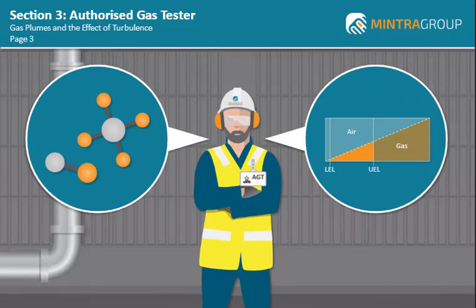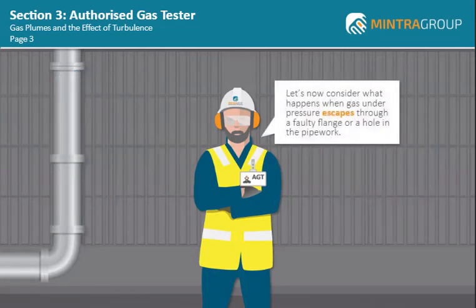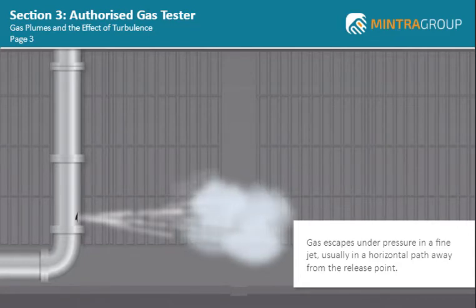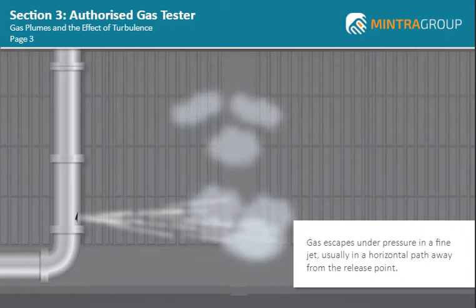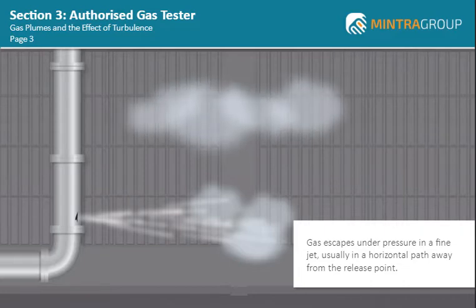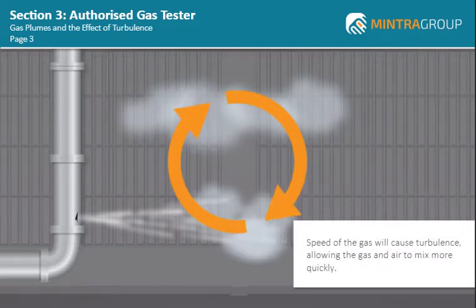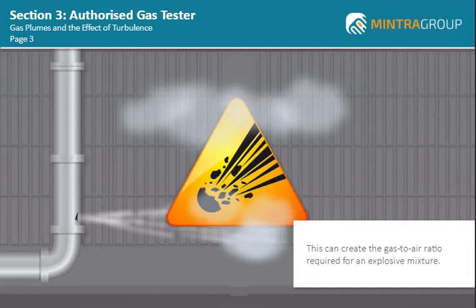Gas and air must mix in a certain ratio before it has the potential to create an explosive atmosphere. When gas under pressure escapes through a faulty flange or a hole in the pipework, the gas escapes under pressure in a fine jet, usually in a horizontal path away from the release point. But gradually, if it is a light gas, it will start to rise. As the velocity of the gas release reduces, the gas plume will spread out as it moves upwards. The speed of the gas moving through the air will cause turbulence, allowing the gas and air to mix more quickly, which in turn can create the gas-to-air ratio required for an explosive mixture.